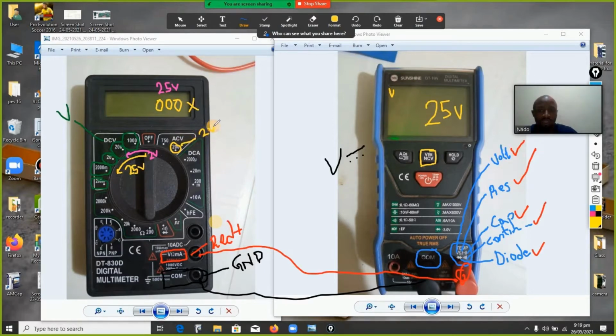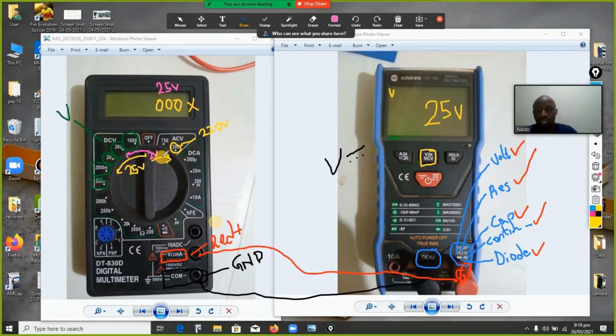...volt AC, I can't have the value on my screen because the value I've set here, the tuner, is lower than 220, so I won't have the voltage. Instead, if I'm to get it, I'll have to tune this probe to around 750 here. So if I check here now, I'll have my voltage at this point, which is 220 volts.